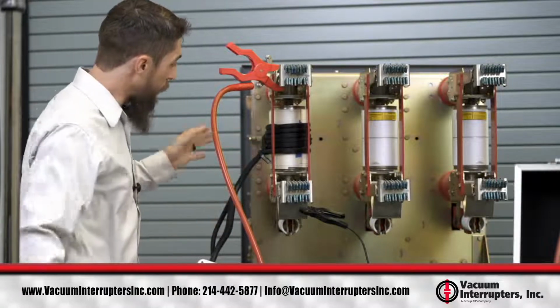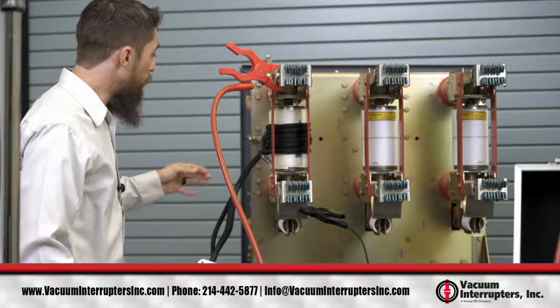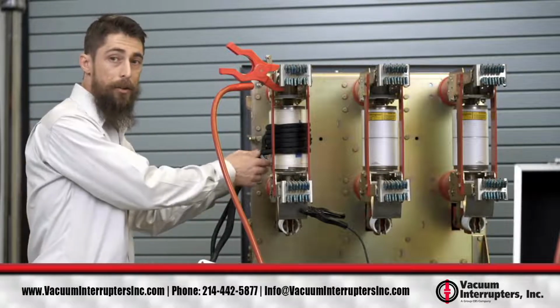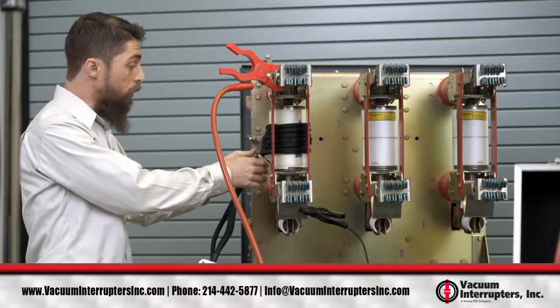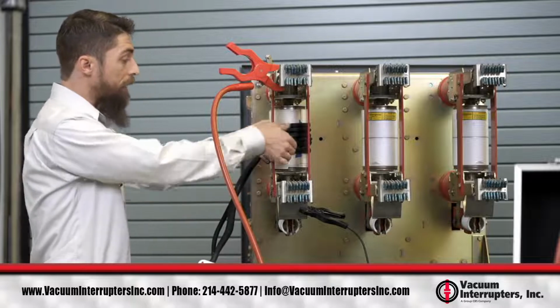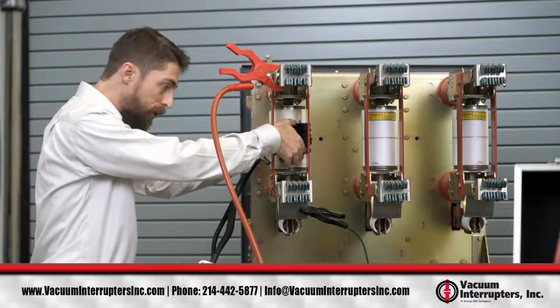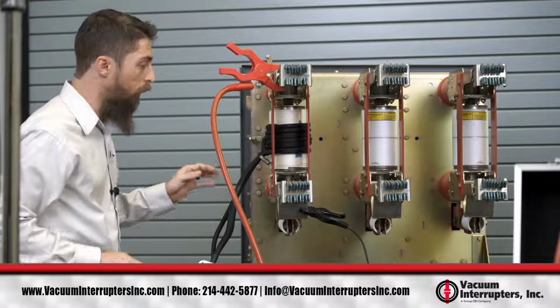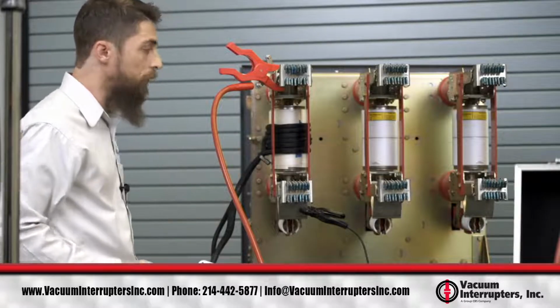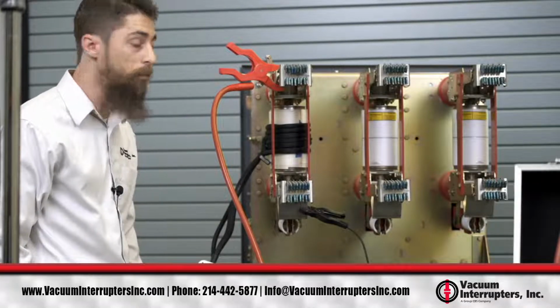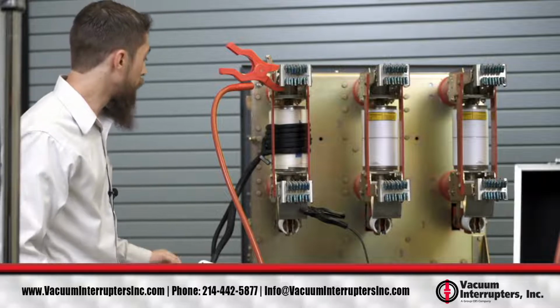So you want to get, again, at least 5 wraps. You want to cinch the coil tightly so that there's no slack, and you don't want the coil to slip down while you're doing the test. So you want the coil centered approximately where the contacts are going to be inside the vacuum interrupter.